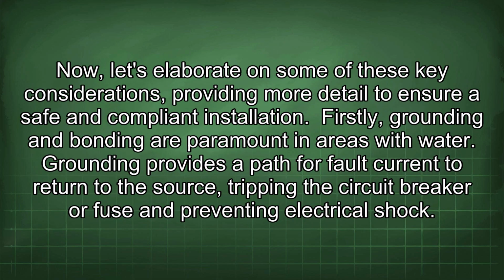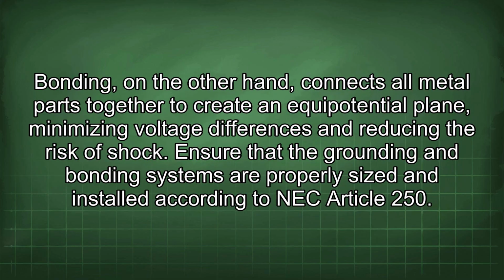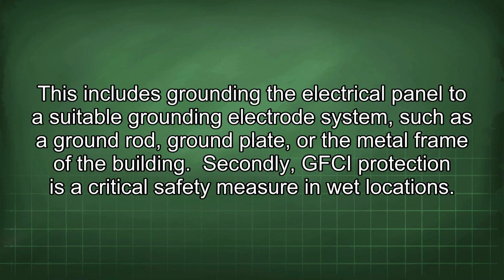Now let's elaborate on some of these key considerations, providing more detail to ensure a safe and compliant installation. Firstly, grounding and bonding are paramount in areas with water. Grounding provides a path for fault current to return to the source, tripping the circuit breaker or fuse and preventing electrical shock. Bonding, on the other hand, connects all metal parts together to create an equipotential plane, minimizing voltage differences and reducing the risk of shock. Ensure that the grounding and bonding systems are properly sized and installed according to NEC Article 250. This includes grounding the electrical panel to a suitable grounding electrode system, such as a ground rod, ground plate, or the metal frame of the building.